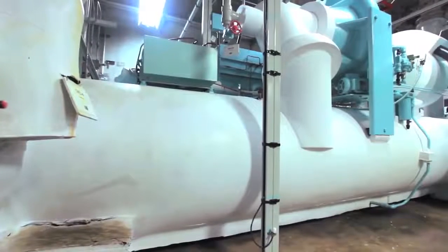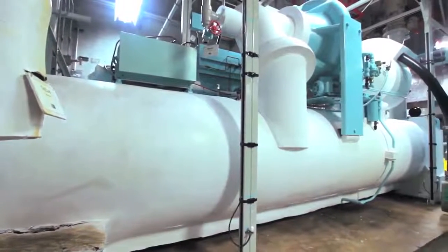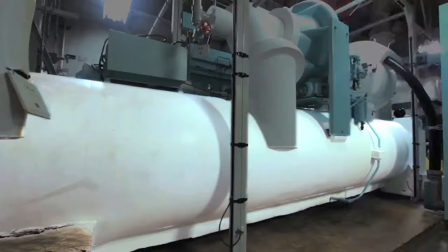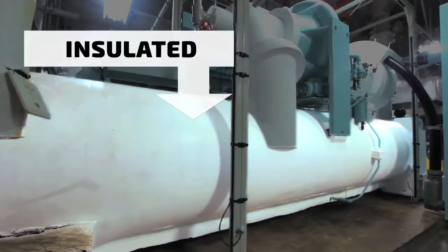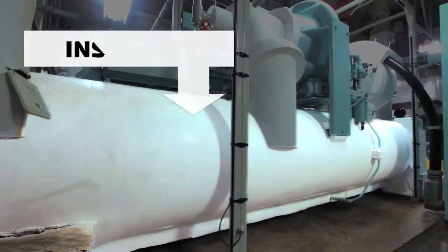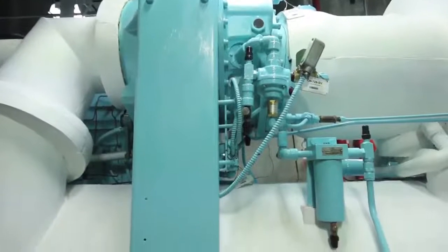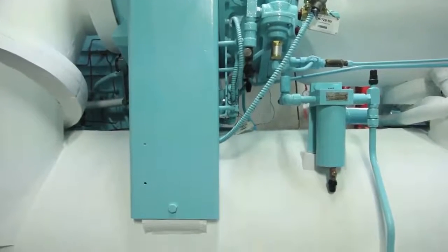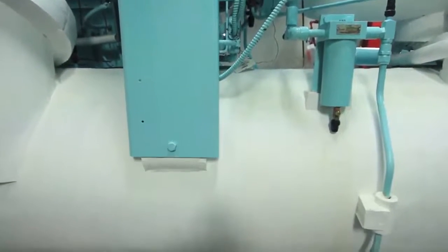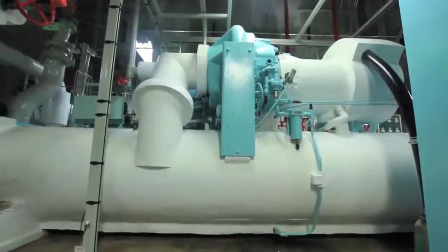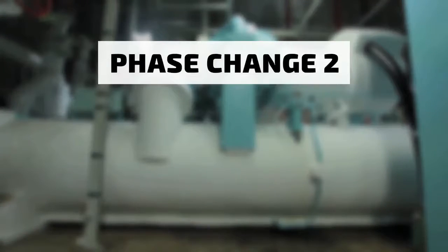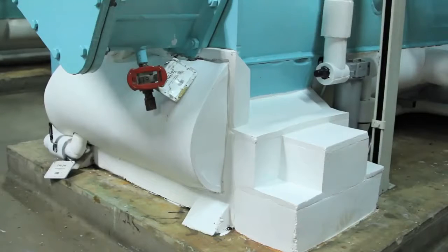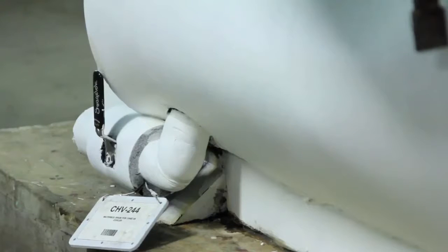As you can see here, all of the lower portion of this machine is insulated to minimize the heat transfer from the environment and reduce the amount of sweating on the steel surfaces. The evaporator is under lower pressure where the refrigerant boils and removes the heat of the chilled water system. This chilled water passes through the tubes in the cooler/evaporator. This is the second phase change. Once the refrigerant passes through the evaporator and completes the second phase change, it is then routed back into the suction side of the system.